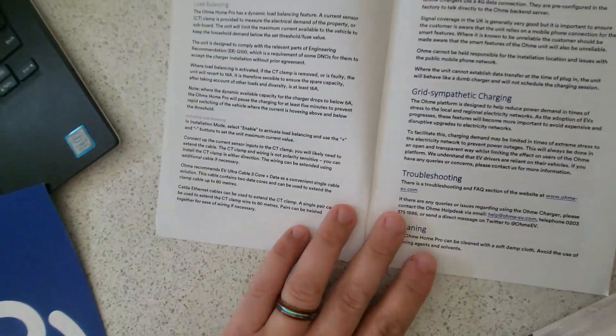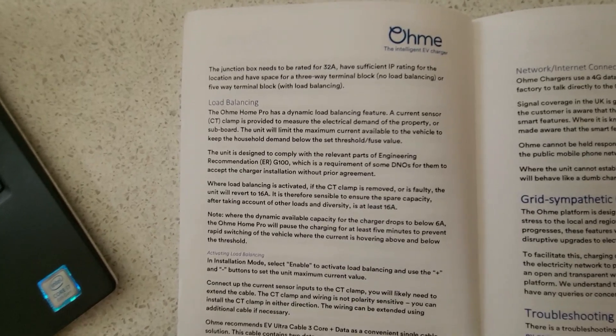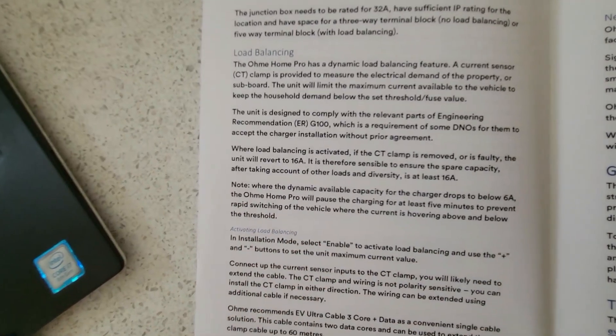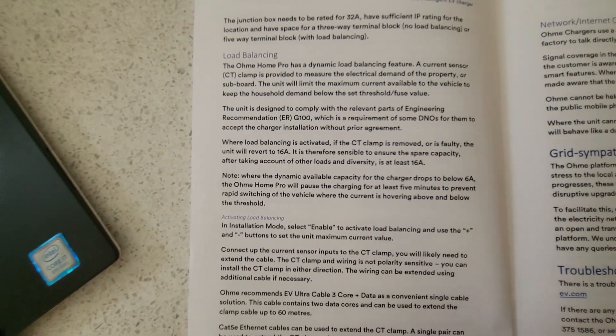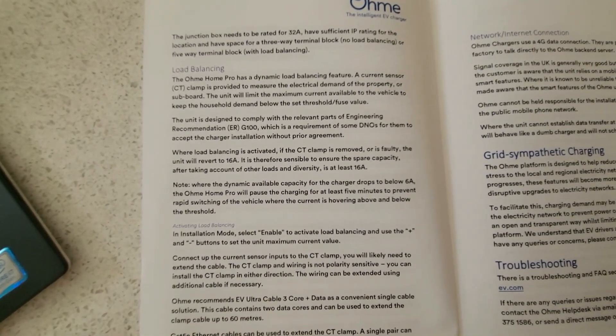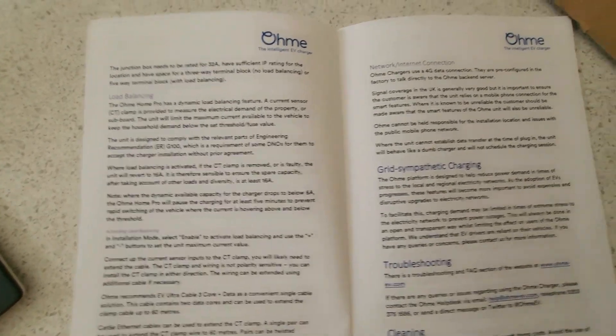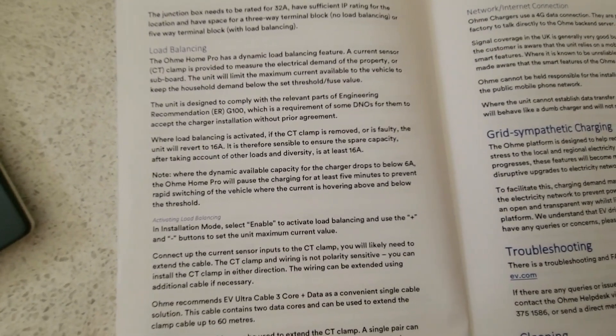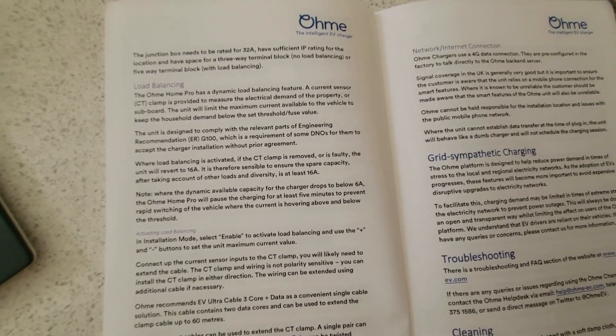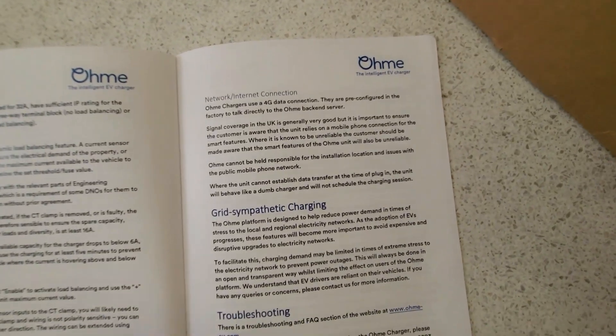The rest covers load balancing and how the CT clamp works. Where load balancing is activated, if the CT clamp is removed or faulty, the unit reverts to a 16A charge rate as a safe state. So if your CT breaks down or someone unclips it, there's no danger of the service fuse ever being at risk — customers will be on the phone about slow charging rather than after the service fuse has gone pop.